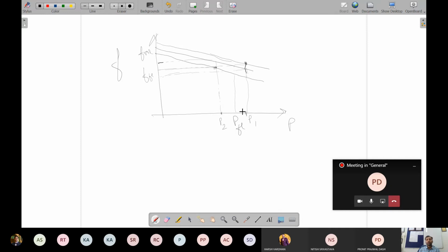So the idea is that if the power demand is shifting either to the higher side or to the lower side, accordingly this FNL, the no load frequency, needs to be adjusted. If your power demand is increasing, you increase this as well, and then you shift the graph up so that the operating frequency is the same. In the same way, if the power demand is decreasing, then you shift this one down so that again the operating point remains the same.